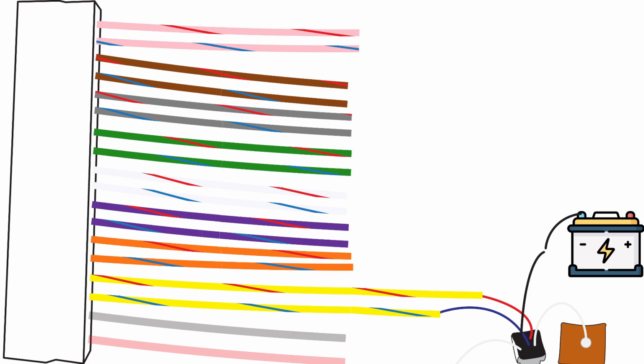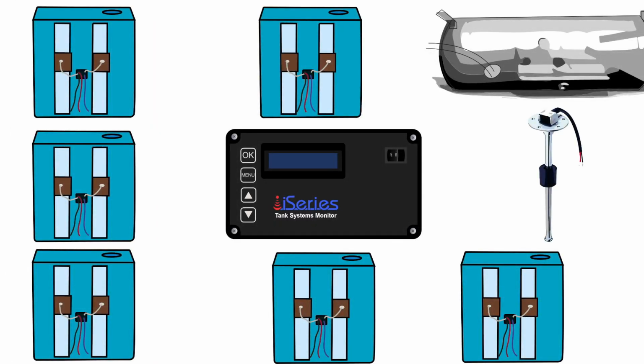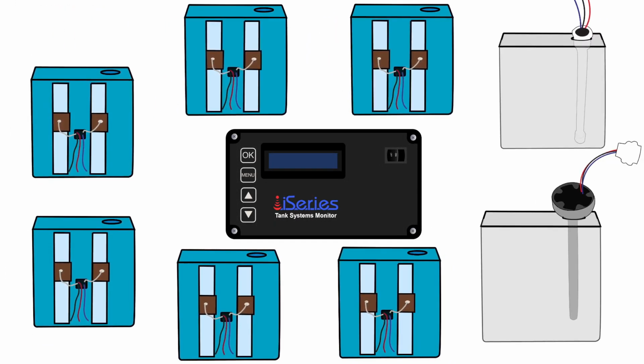Resistive sensors. Note that on a standard iSeries panel, tanks 7 and 8 are only for use with resistive sensors, such as those found in propane tanks pre-equipped with a 90 ohm sending unit or other resistive sensors like float sensors. If you would like an iSeries panel that can use all 8 tanks with standard Moda sensors or interior rods, you can order the Integrity 8 version with that modification.